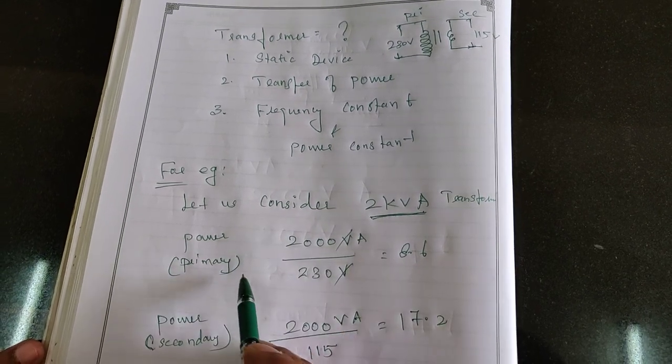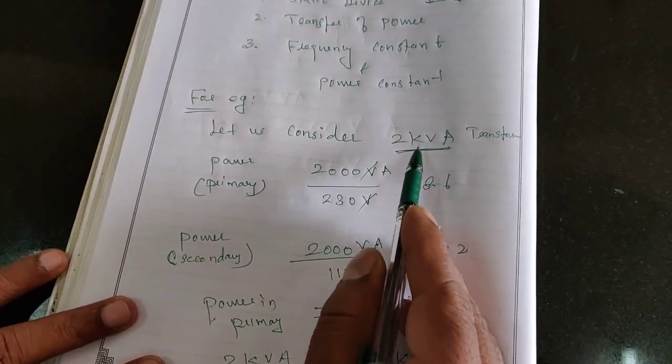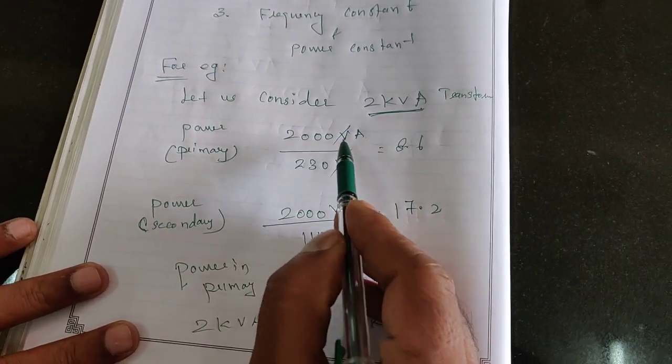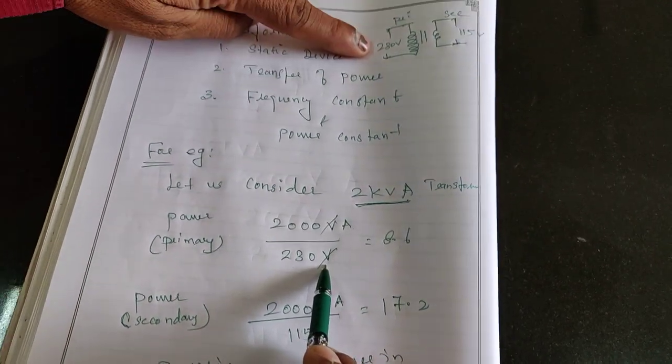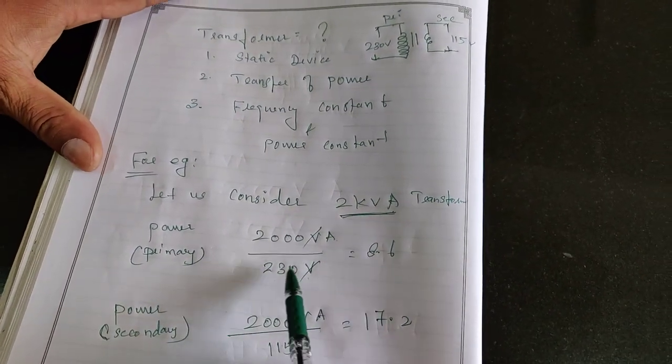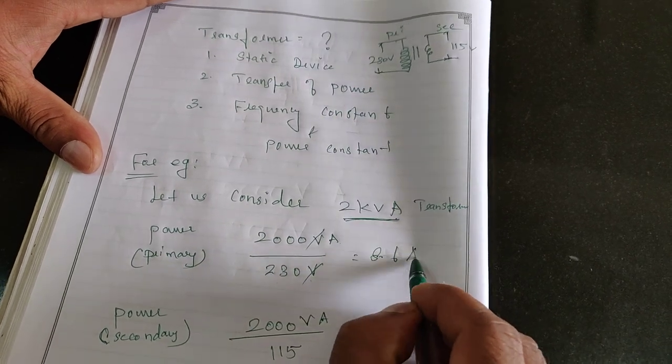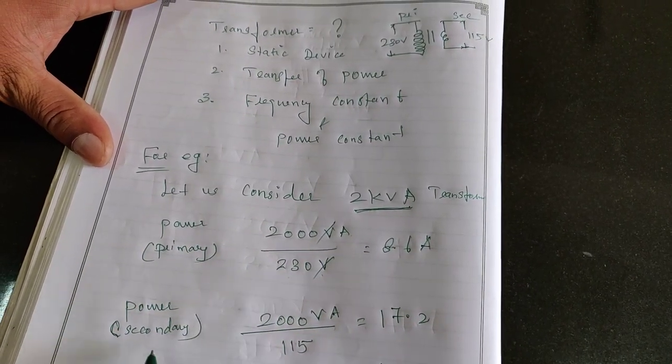Now, we will see here, 2000 volt ampere, 2 kVA means 2000 volt ampere divided by 230 volt which is my primary voltage. Therefore, the current in the primary side is 8.6 amperes.